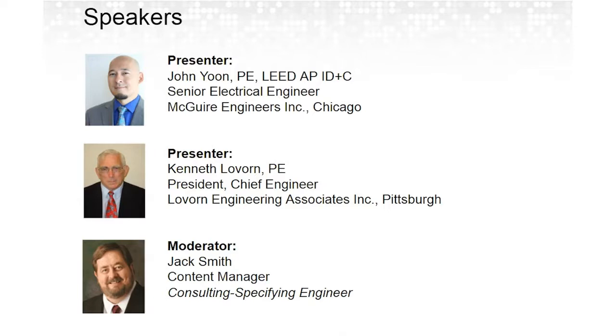Could you further describe transformer isolation and passive harmonic filters? I know you touched on this, but could you elaborate a little bit more? Yeah, thanks, Jack. The transformer isolation, I believe that the question came in on, was for drive isolation transformers. The impedance of the drive isolation transformer under harmonic applications is not great enough to actually reduce the harmonics to an acceptable level, particularly on 6-pulse VFDs. And so the way to do that is to use a passive harmonic filter. You can use active harmonic filters, but I've found that the passive harmonic filters will get you down to 5% total harmonic distortion without any real difficulty, and they're generally less expensive.